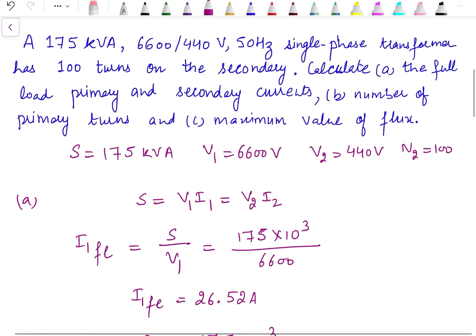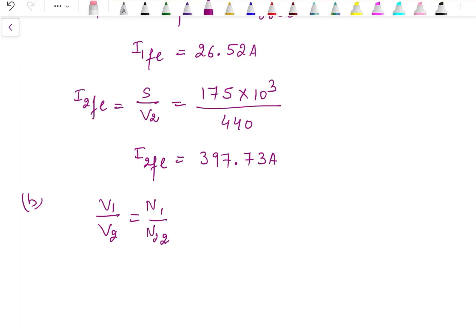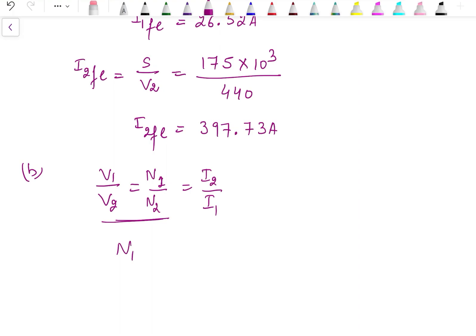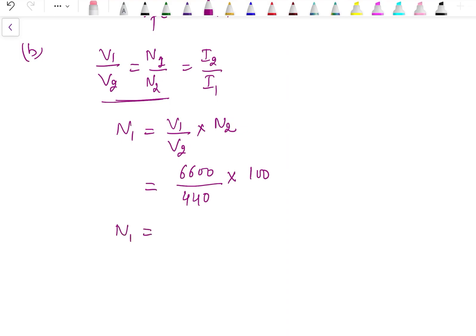In the second part, we need to calculate the number of primary turns. We know that for a transformer, V1/V2 = N1/N2 = I2/I1. Using V1/V2 = N1/N2, we get N1 = (V1/V2) × N2 = (6600/440) × 100, which gives us N1 = 1500. So the number of turns on the primary side is 1500.